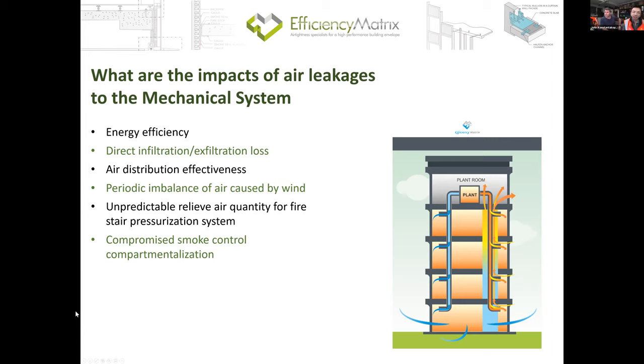Okay. First come first, I know that today we are mostly talking to building services engineers, and just a very, very brief why it relates to you, because air leakage can affect the energy efficiency of all the building services performance. And the first impact is very obvious, the direct infiltration, exfiltration loss because of the air moving in and out from the ambient. But it also will affect the air distribution effectiveness, especially the unpredictable nature caused by wind. Sometimes the wind is coming from the north side and you find it hard to push your conditioned air into the north zone, but half an hour later, the wind direction changes and it messes up your control system. Not just that, it also causes periodic imbalance caused by wind.